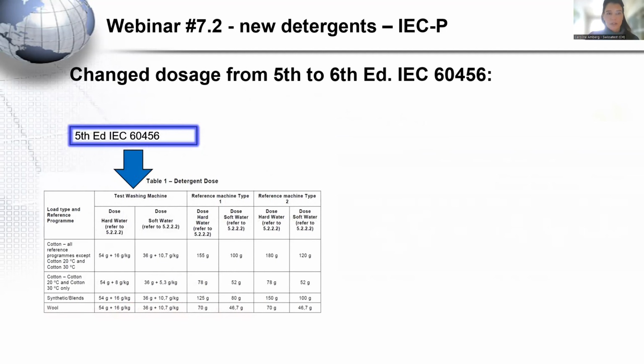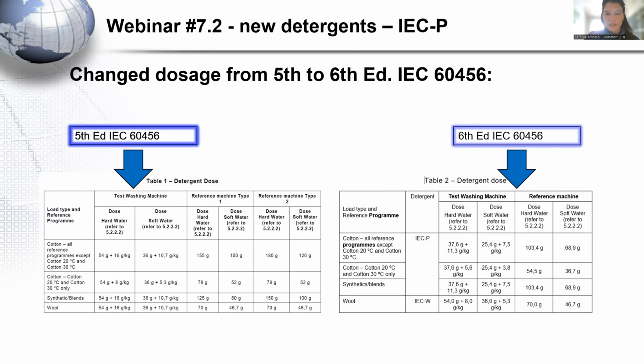Good. Then the changed dosage. You see here on the left-hand side the dosing table for the 5th edition, and then on the right-hand side the dosing table for the 6th edition. As you can see, for example, when we have a look at the reference machine with hard water, 40 degrees or 60 degrees, we have here 150 grams, whereas in the 6th edition we have, for the same condition, 103.4 grams. So it is really a decrease of the detergent amount.